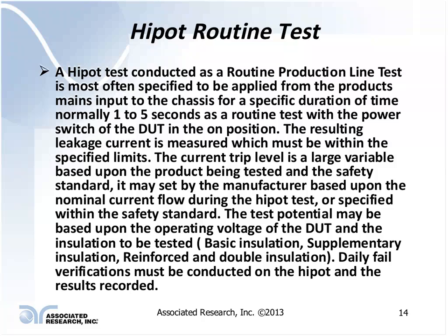With connecting up products, if we're talking high-speed production lines, sometimes between products you may be talking 10, 20 seconds from one product to another. So these things are moving down the line very, very quickly. So you want to test these things as quickly as possible, but yet you want to make sure that the insulation is still being tested properly.